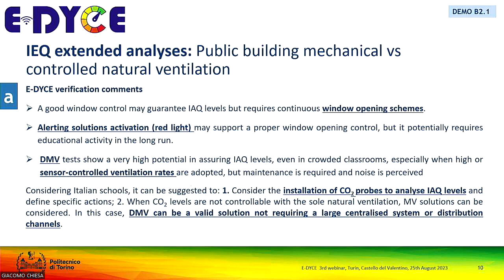But clearly in this case, monitoring is important to avoid, on the one side, over-ventilating in winter, like arrives immediately after COVID when the request is to leave the window open. And you see immediately that the heating system increased the consumption, and the average temperature in the room fell down in some way, because the dimension of the radiator is in line, no? We can say.